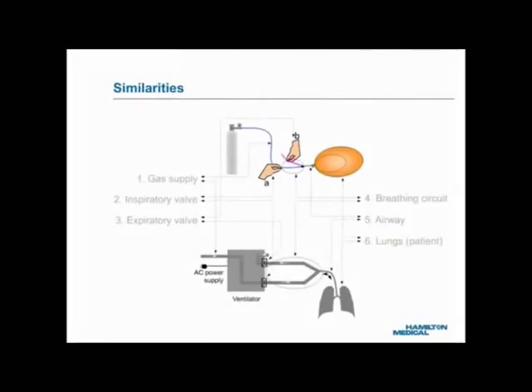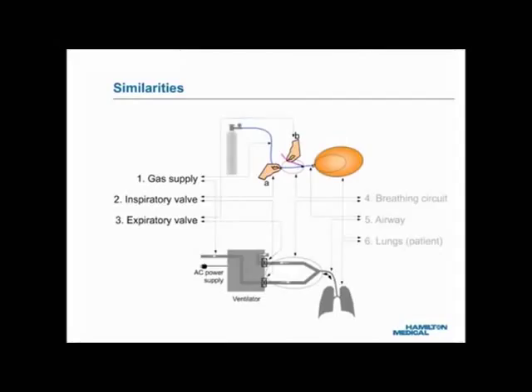The balloon model is highly comparable to a real ventilator system. One: the cylinder corresponds to the high-pressure gas supply — a ventilator system needs the supply of two gases: high-pressure oxygen and high-pressure air. Two: hand A corresponds to the inspiratory valve. Three: hand B corresponds to the expiratory valve. Four: the blue and pink tubes between the Y piece and the two hands correspond to a breathing circuit. Five: the blue tube piece between the Y piece and the balloon corresponds to the airway. Six: the balloon corresponds to the lungs of a ventilated patient.